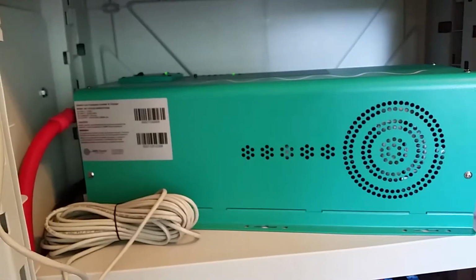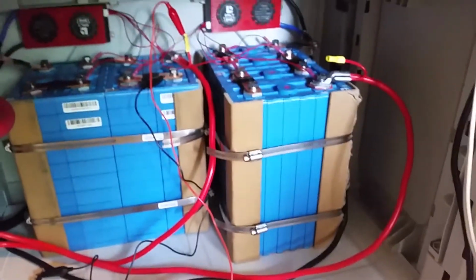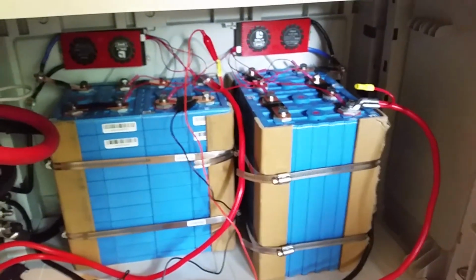But anyway, that's what I've got going on now. We're at 240 amp hours down, 35% left, and 11.86 volts. That's pretty close to the voltage at this inverter charger. We've got about 0.35 to 0.4 volts between here and here, voltage drop.